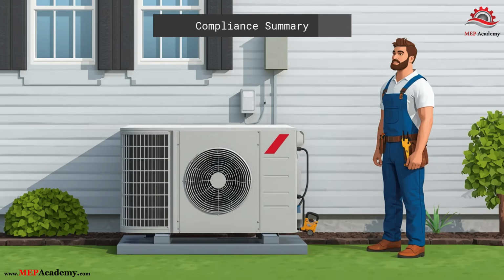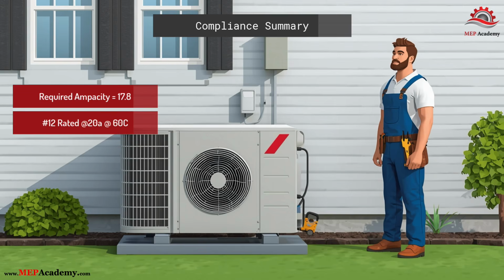Final compliance summary. Let's summarize the installation. Required ampacity, 17.8 amps, MCA. Selected conductor, number 12 copper, rated 20 amps at 60 degrees Celsius. Circuit breaker, 30 amps per the equipment nameplate. This installation meets the NEC requirements for air conditioning equipment. Always verify installations against the current edition of the NEC and local requirements.